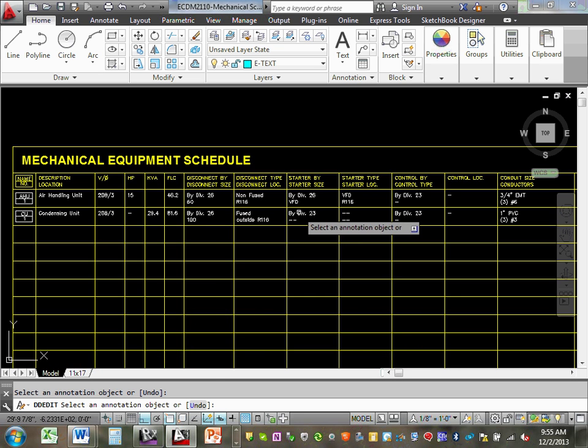This calculation here will summarize everything that you learned with me in the fall as well as in the spring, doing the calculation for the schedule. That's why we did all the motor calculations and so on. I know it's a lot of information. That's what engineers do. When you're stuck, you're going to ask Chad, hey, I forgot how to do the heaters disconnect, Chad, which is continuous load, 1.25. Motors, all your motors, Karen, are exactly like I did. HVAC equipment, exactly like a condensing unit. If it's heaters, 1.25 for everything. Any comments, guys? Any questions?